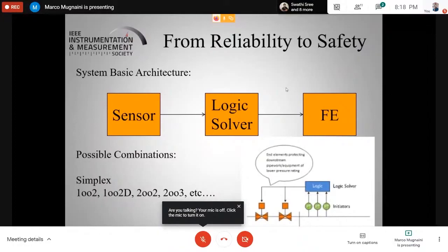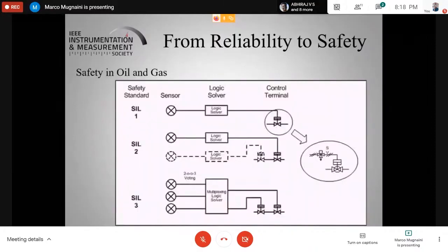This is an example of what you can get in oil and gas. If you want SIL level 1, usually you have a single chain. If you want SIL 2, you should have at least two chains performing independently the same function or covering the same function. And for SIL 3, you should have at least a voting system, a 2-out-of-3 condition, for example, where you have 3 sensors and the logic solver takes a decision based on at least 2 inputs of the same kind.